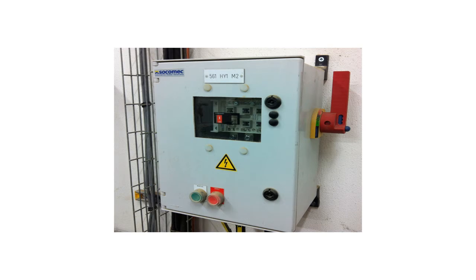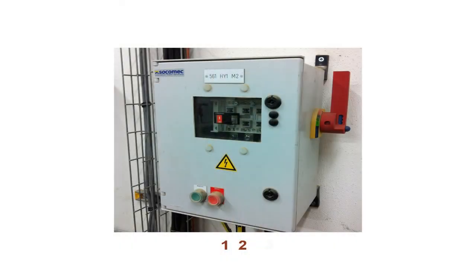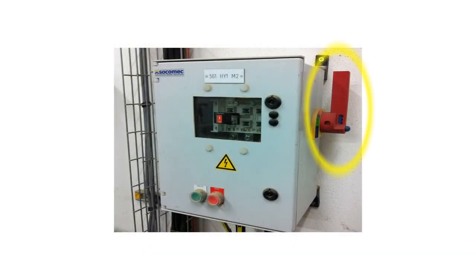On the picture, you can see a typical local isolator switch in an enclosure. The cable connection can be from the bottom or from the top, depending on the arrangement. You need to find at least two cable glands on a local isolator switch. These are connected to the main circuit, the incomer and the outgoing. The third cable could be connected for the control circuit for additional functions like local start and local stop functionalities. The handle of the local isolator switch should be accessible without opening the electrical enclosure. You should be able to identify the direct cable connection from the local isolator switch to the motor or to other electrical equipment it's designated for.